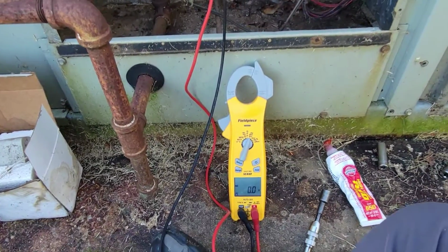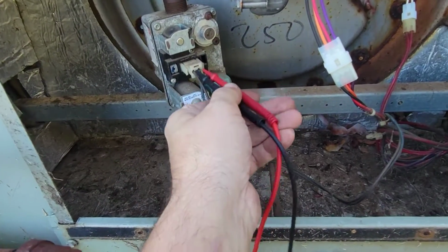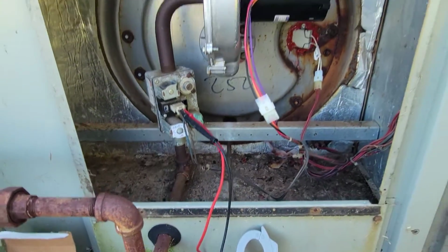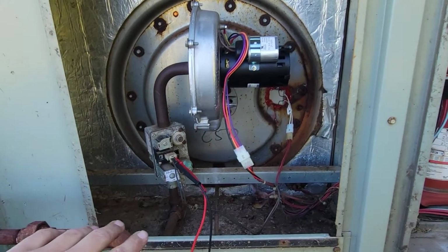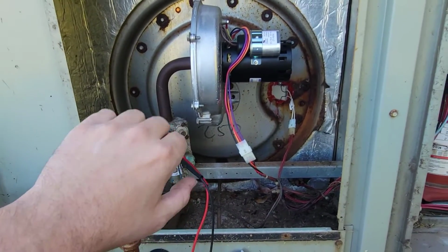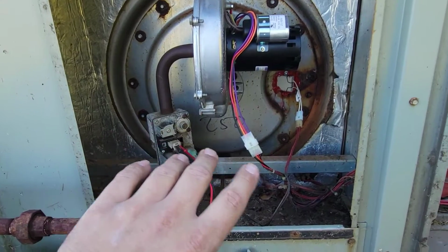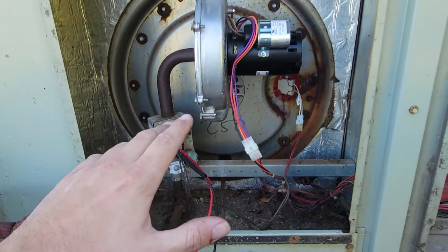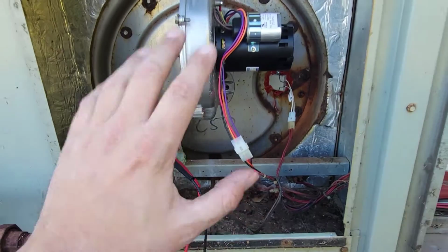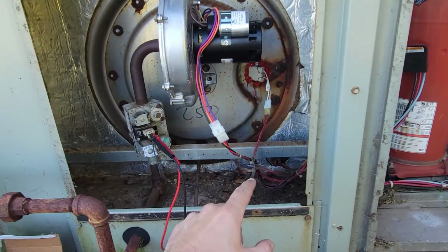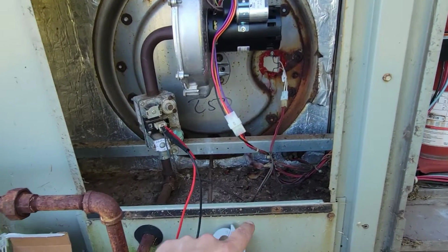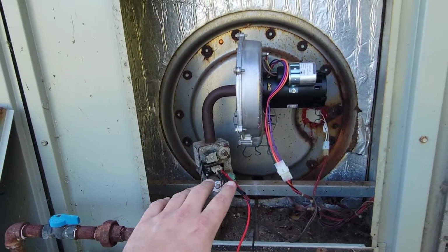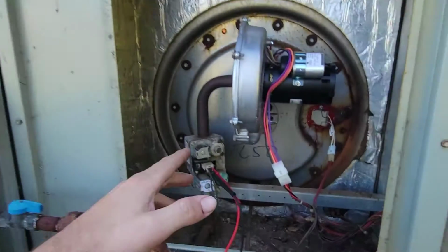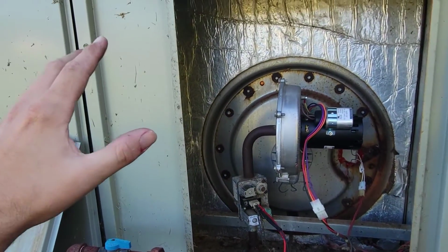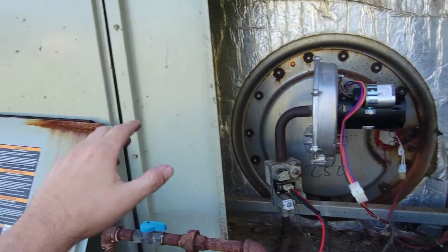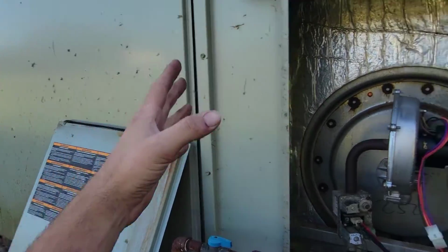All right, so we're fixing to call for heating. I've got my leads measuring the voltage to the coil of the gas valve. Now, sequence of operations. The inducer motor comes on. After the inducer motor comes on, then you have all the safeties. Usually on residential equipment, you have a pressure switch. On this unit, you do not. You've also got a rollout switch, which detects flame rollout. You've got a limit switch, and there's one in this cabinet over here, in case you have a high temperature situation. Limit switch breaks open, indoor fan stays running.